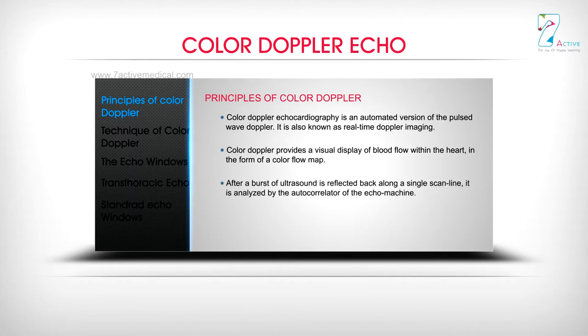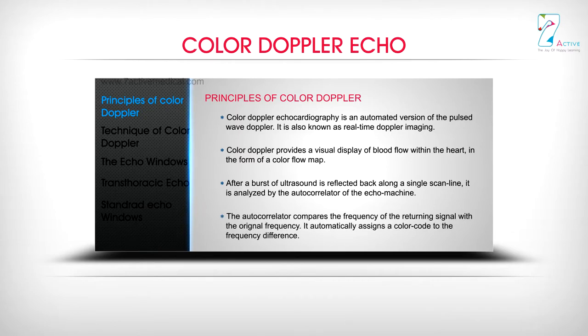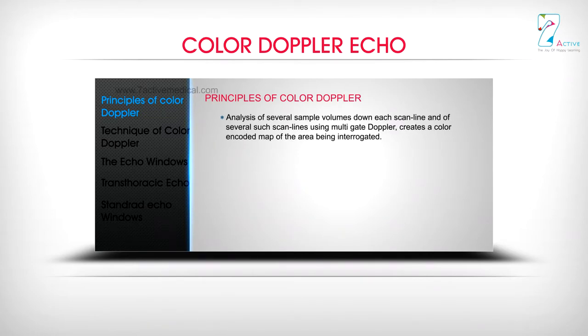After a burst of ultrasound is reflected back along a single scan line, it is analyzed by the autocorrelator of the echo machine. The autocorrelator compares the frequency of the returning signal with the original frequency and automatically assigns a color code to the frequency difference. Analysis of several sample volumes down each scan line using multi-gate Doppler creates a color-encoded map of the area being interrogated.